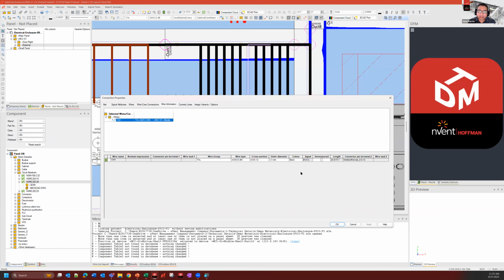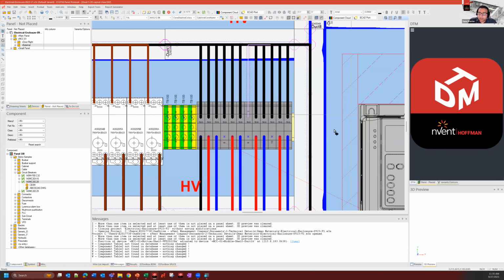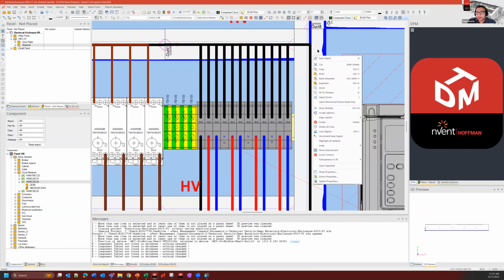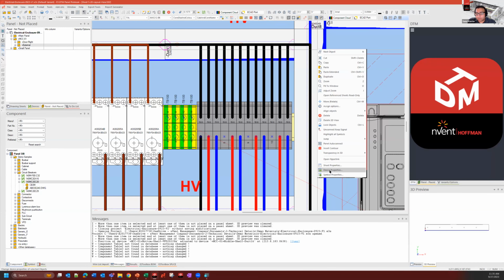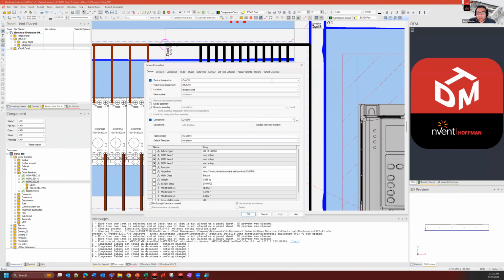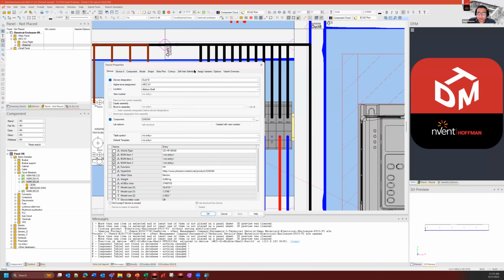So again, very quick and easy to route everything inside the enclosure. But you'll also notice these blue areas inside the project, inside the duct—that's the fill ratio, showing how much wire is in there. There's a dotted line that tells me if I select wires beyond that, it's going to warn me that there are too many wires in there. That's the limit I've set.